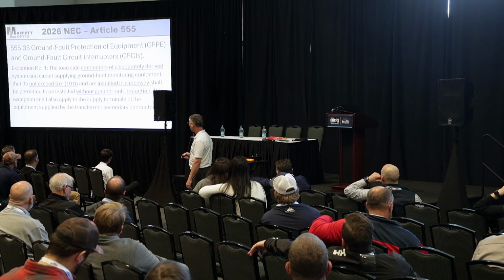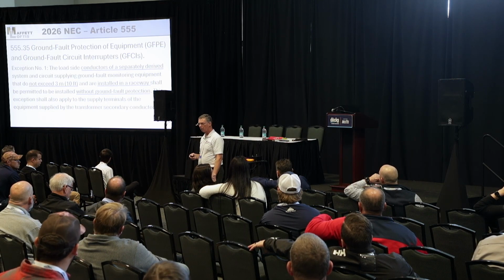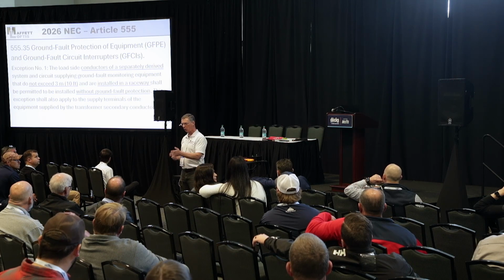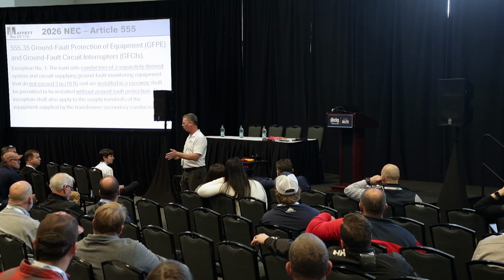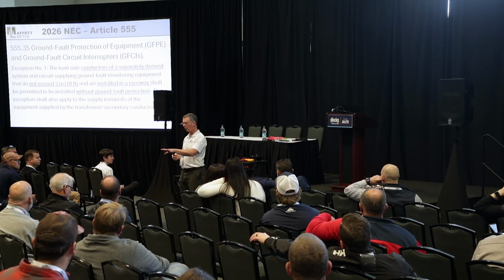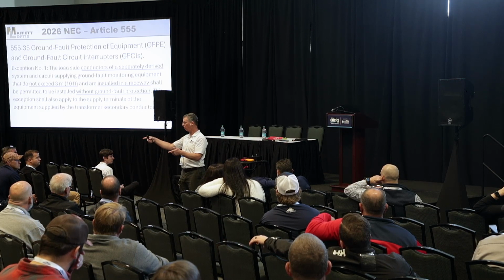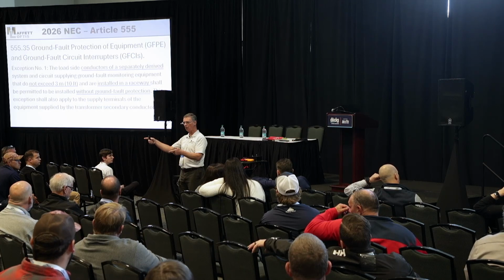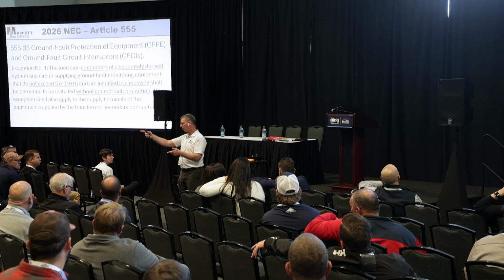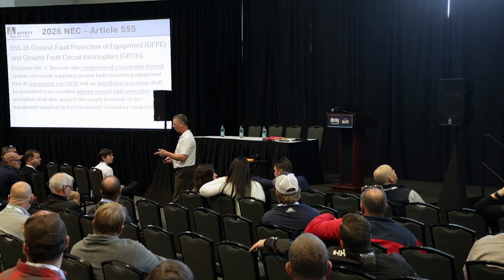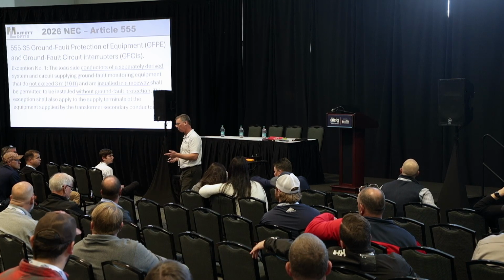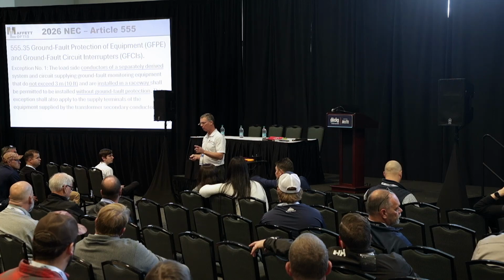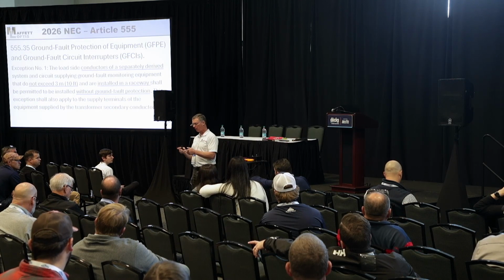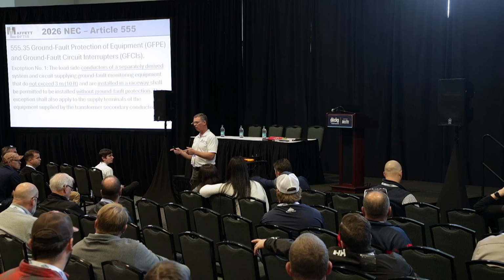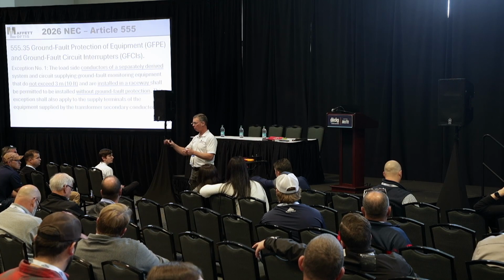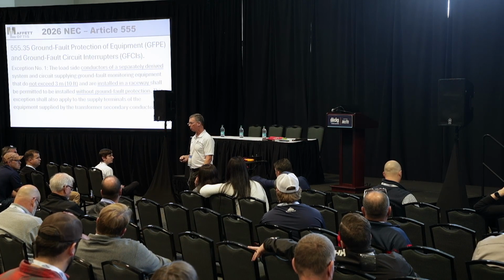And it can be installed without GFPE. Think about a generator. It's a separately derived system. If you have a generator, and I've been installing or designing generators out on the floating dock, from the generator to the first point of overcurrent protection doesn't have to have GFPE, because the manufacturers, like Generac, can you get GFPE? I don't know if you can get GFPE in a Generac. There's a booth out there with E&W about Generac generators, but it's very difficult, like pulling teeth, to get them to put GFPE in it. But as long as that wire is less than 10 feet and it's in a raceway, we can get to a panel. Those are the types of systems I'm talking about.